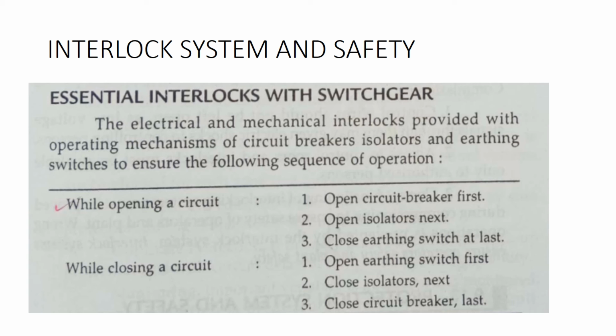And suppose we are not closing the earth switch, and without closing the earth switch we go for maintenance. Sometimes a person will get electric shock because charge will be there in the transmission line. So we have to discharge it by closing the earth switch. For closing the circuit, the sequence is like this. First we have to open the earth switch. Then we have to close the isolator. Last only we have to close the circuit breaker and the line is charged.